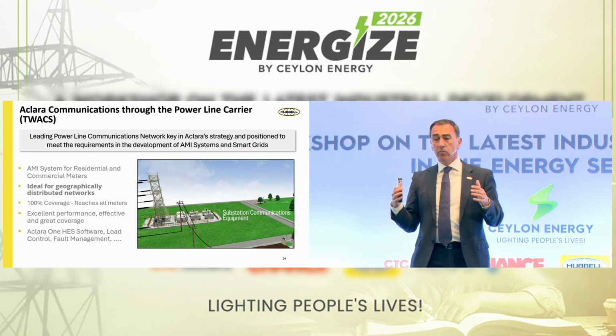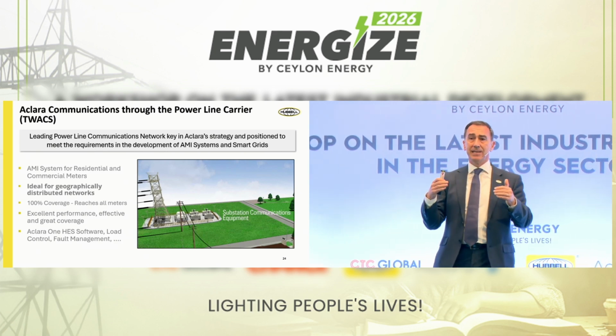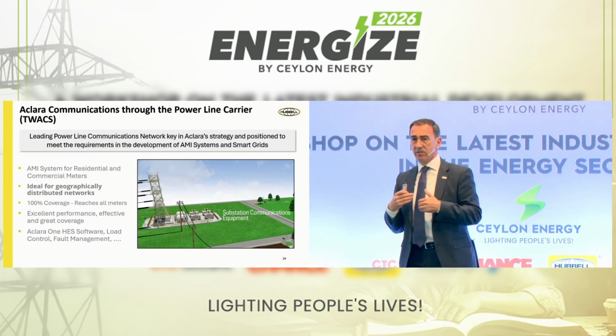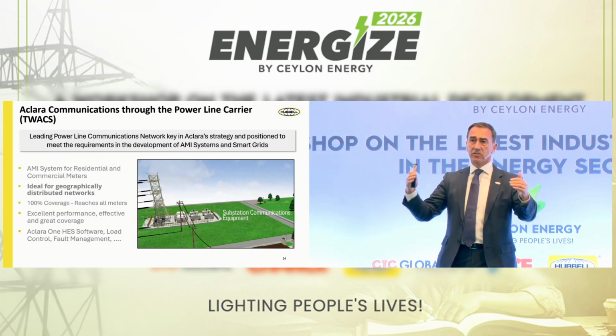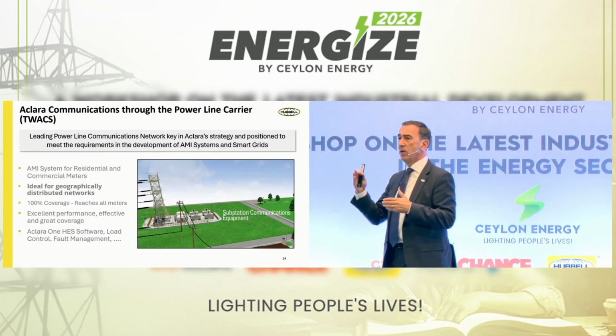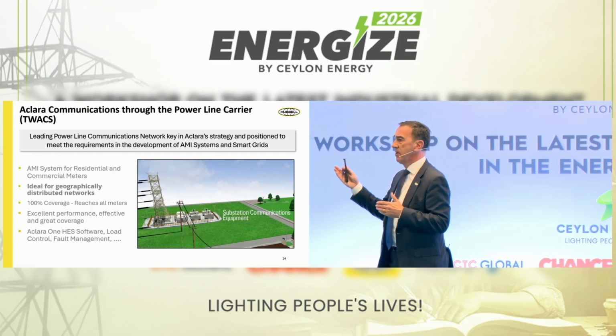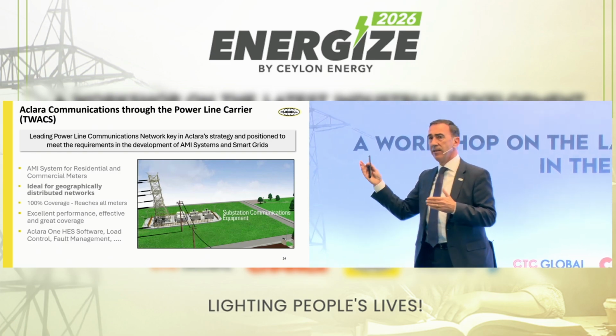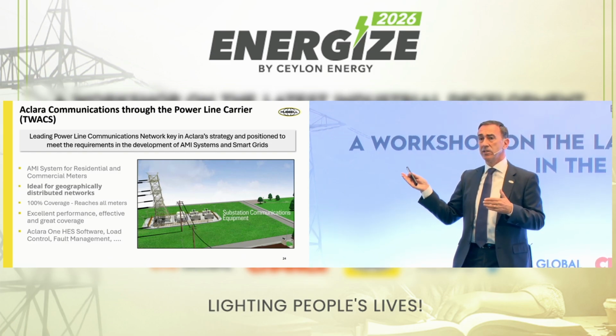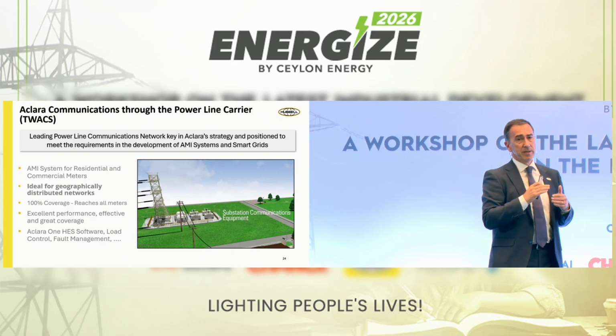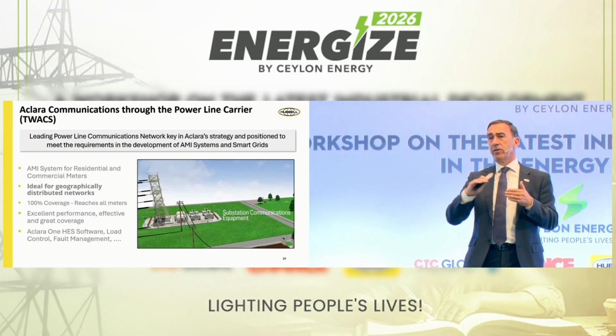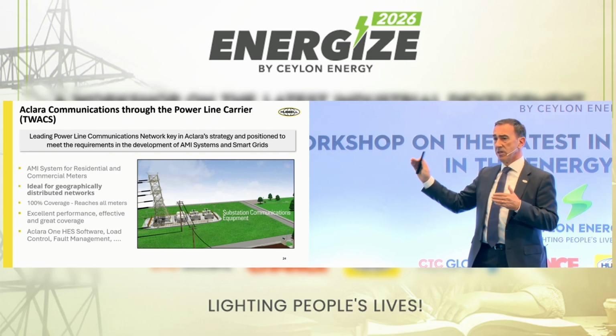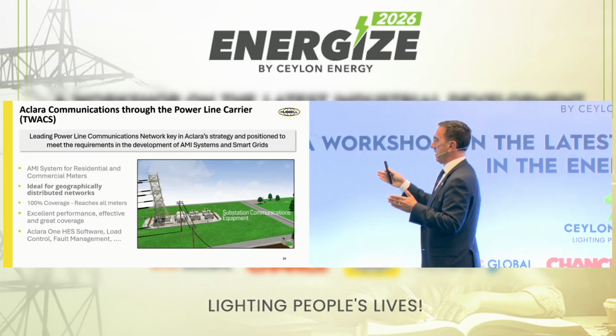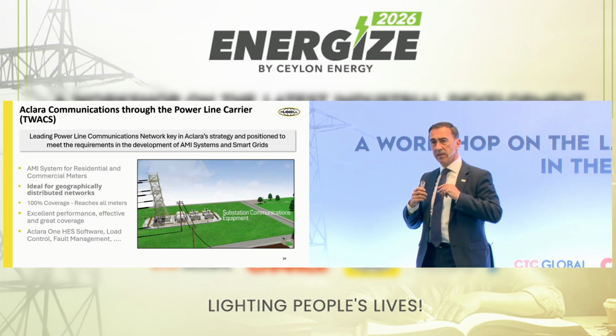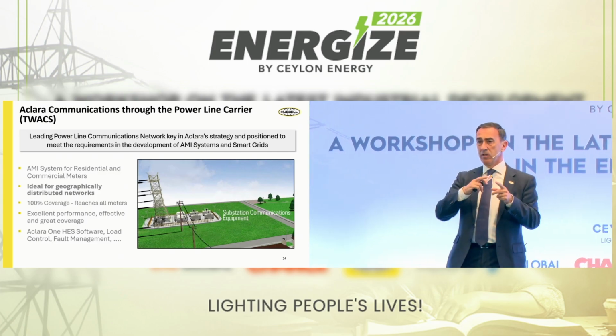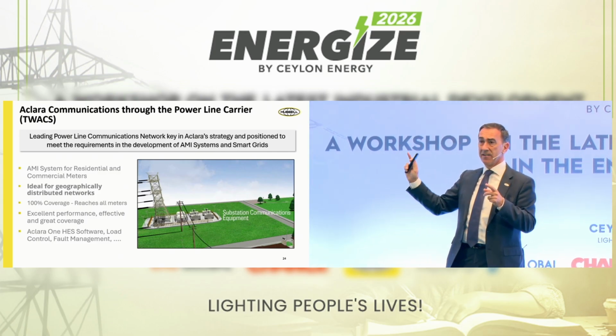All the communication equipment is built inside the substation, within its boundaries, so you don't need additional equipment outside, like gateways or other PLC technologies need, because this PLC signal goes through the distribution transformers. You have the medium voltage transformer, you send the TWACS signal through the cable, it goes through the distribution transformer and reaches the meter.